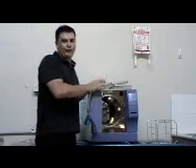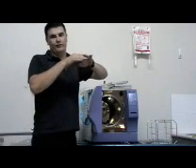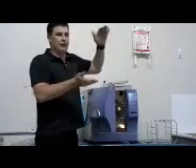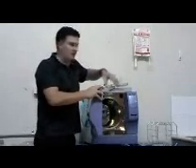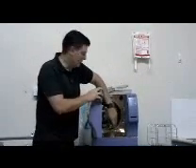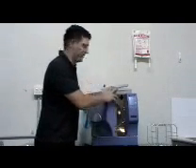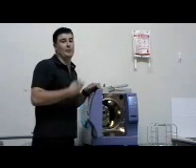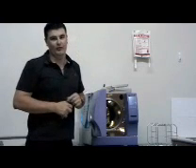You are not actually levelling the unit itself — you are levelling the unit relative to the bench top that you have got it sitting on. The two have to be one entity. It is not a matter of using a spirit level; it is important to make sure the water does touch the probe correctly. This may be a process you have to repeat several times to get it accurate, but it is important to get it right.